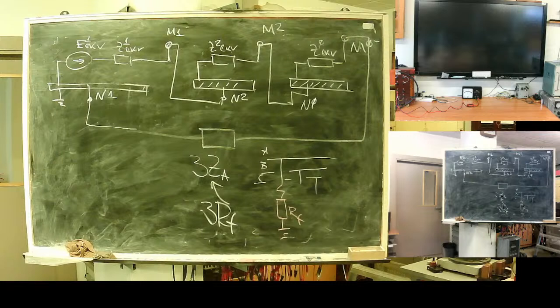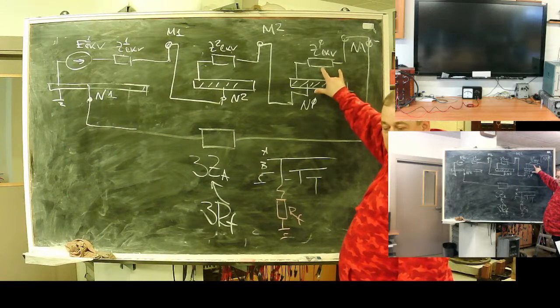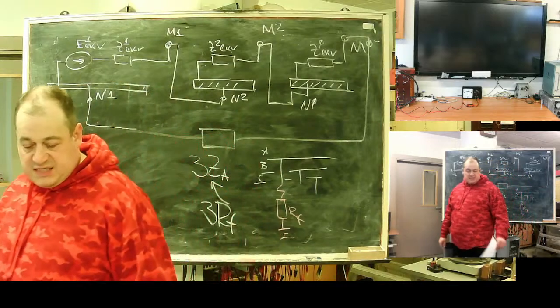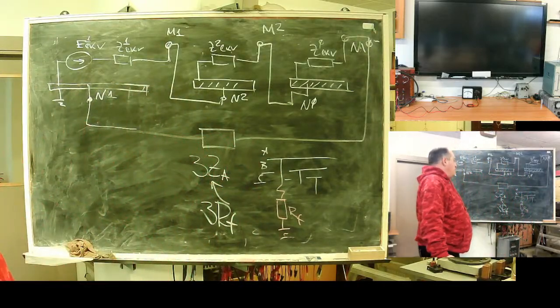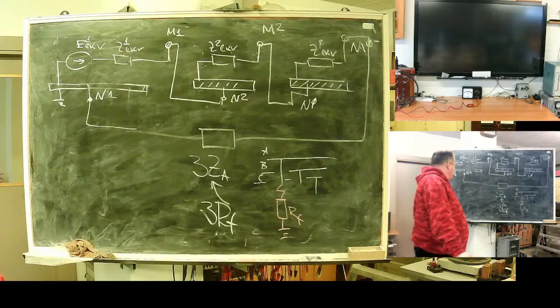When we speak about ground fault protection or earth fault protection, these schematics will be paramount. Without this part, successful analysis of earth fault protection is simply futile. It's an illusion that analysis can be performed without direct and deep knowledge of the zero sequence network.